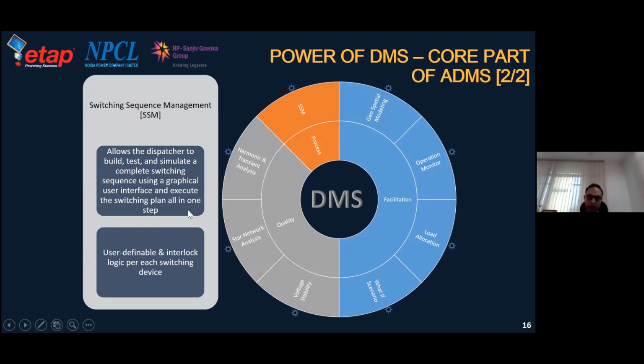In this particular module, we first have to define the switching sequence. A very basic example: in an on-load condition, my isolator should not be switched off. First we have to do the switching off of the circuit breaker, then only the isolator. So all those switching sequence related operations, including finally making the earth of every conducting element on which a particular person has to work.